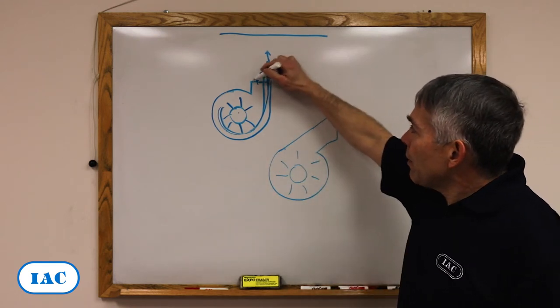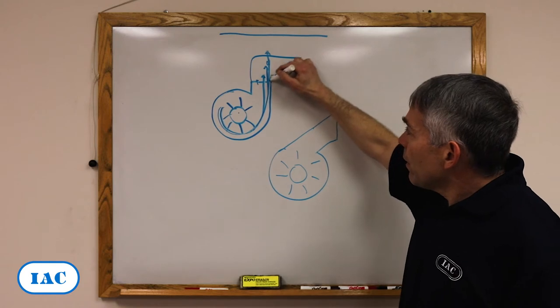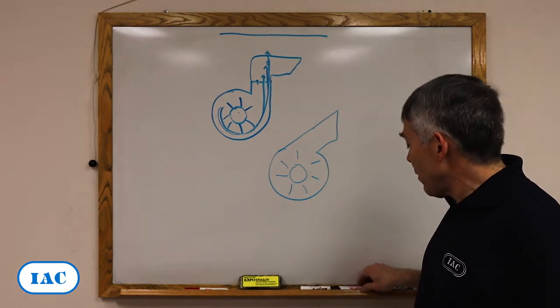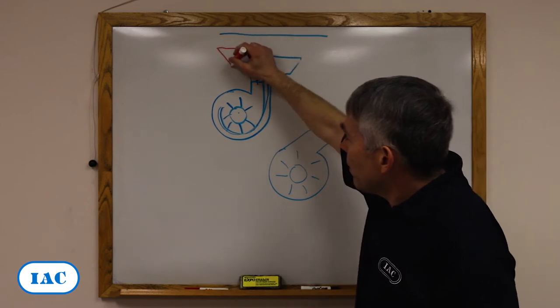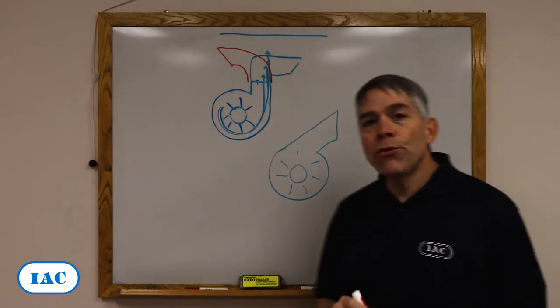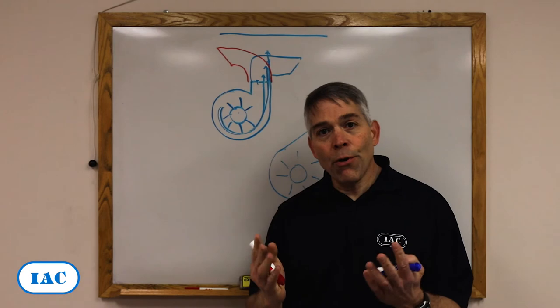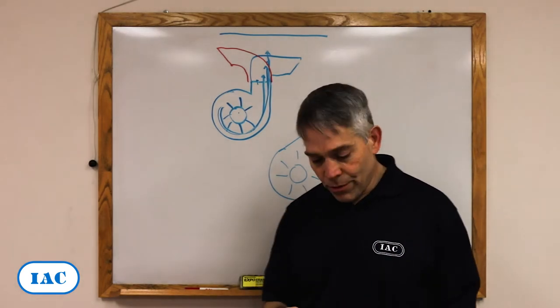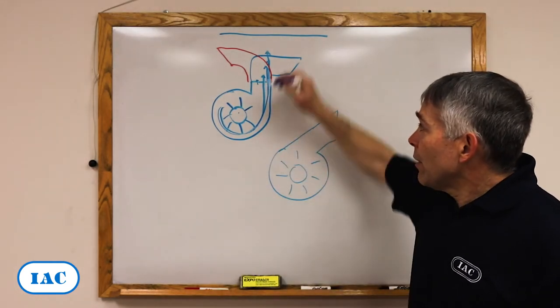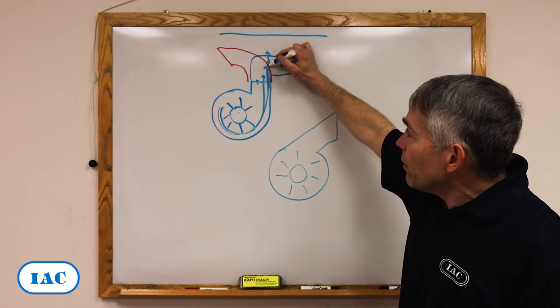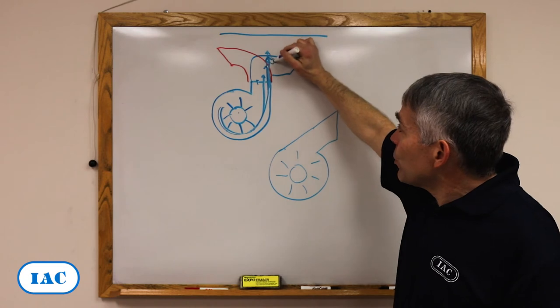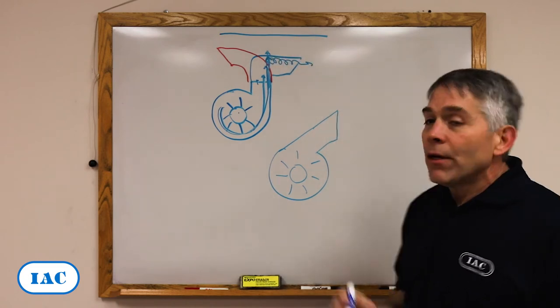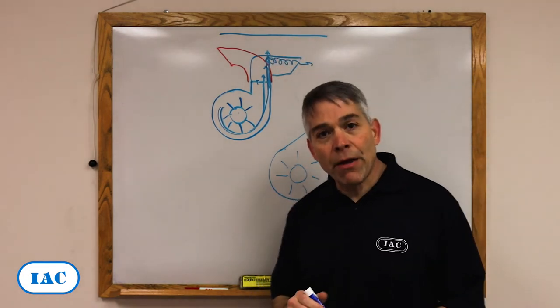You may think that this is appropriate, or somebody else may think that this is appropriate. Which way would you use now that you know how a centrifugal fan works? Picture both cases. You have most of the high velocity on this side, this comes and hits a brick wall straight off, which generates losses, and the fan simply loses capacity.